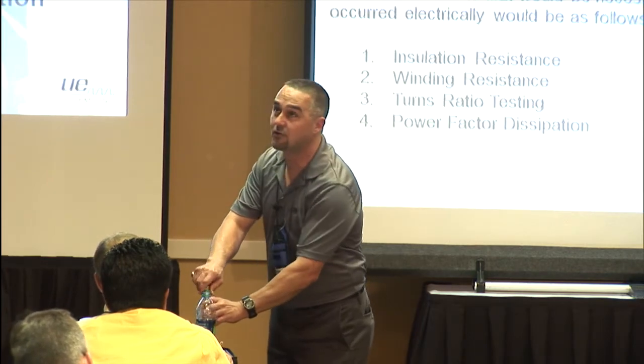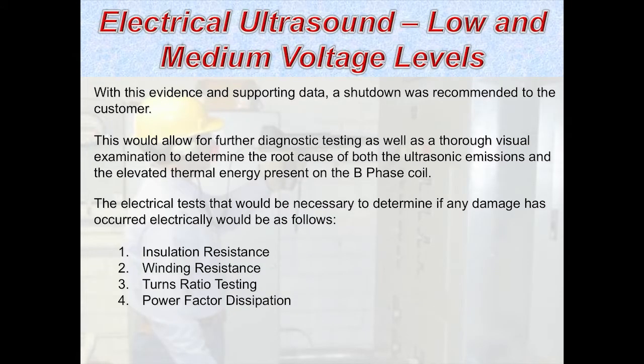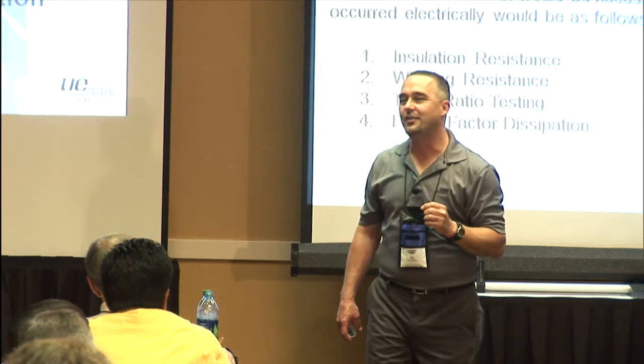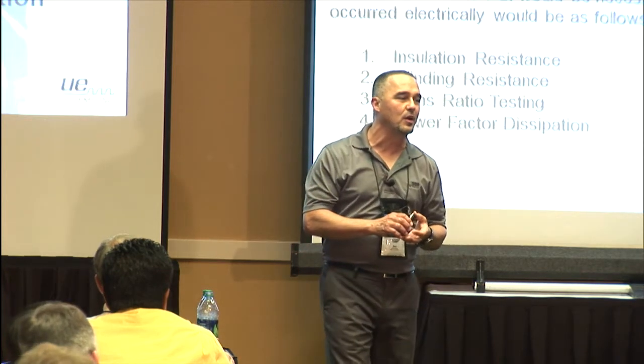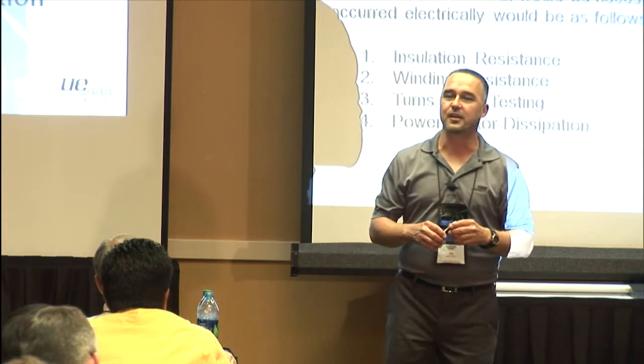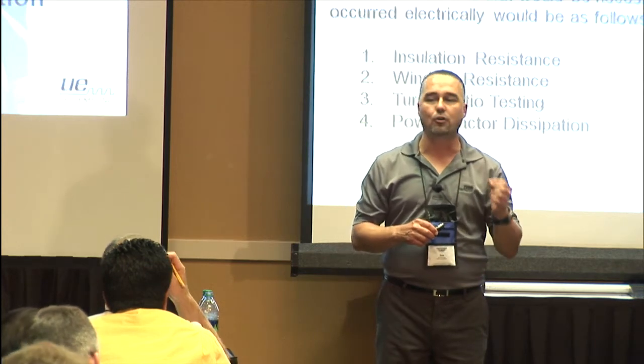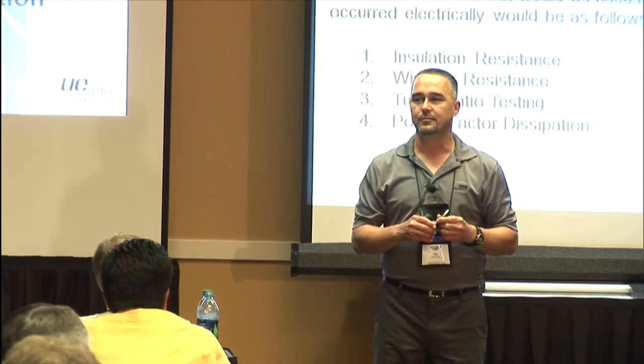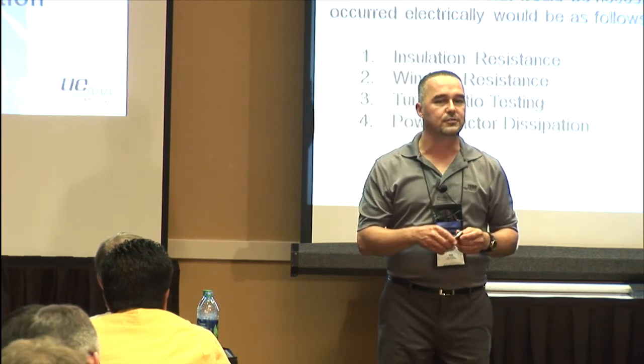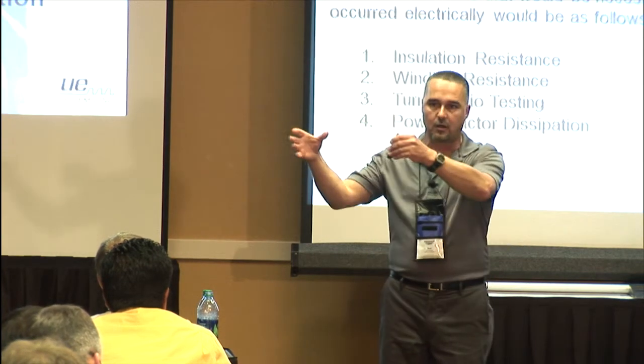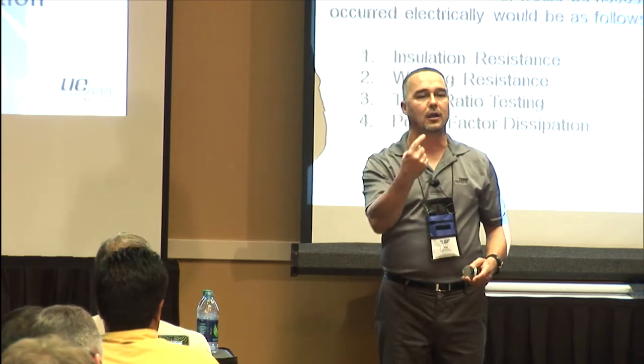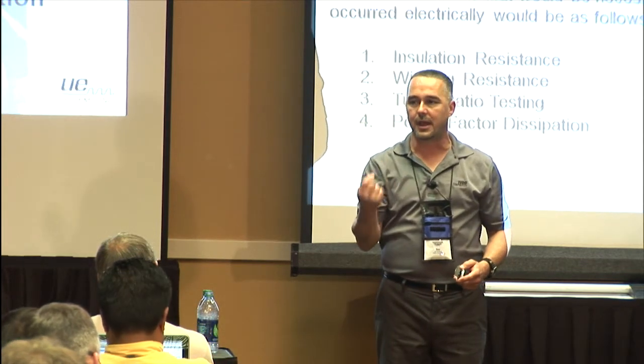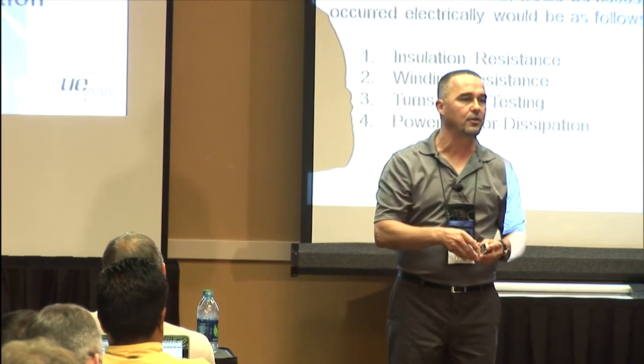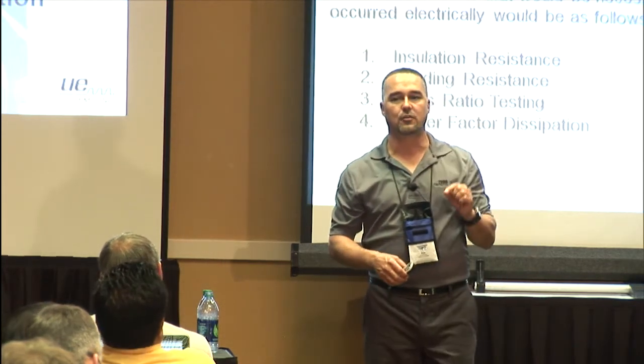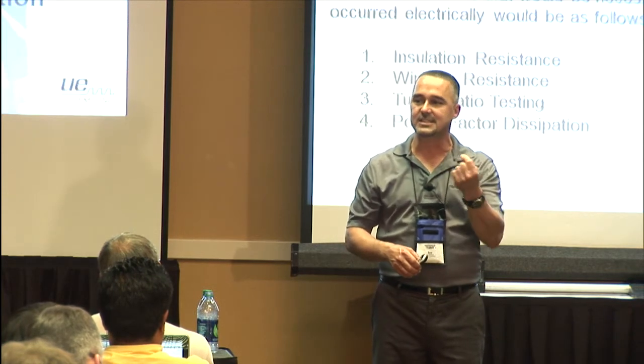The other one I got on here is called turns ratio testing. Has anybody ever heard of that? Good. Those of you who have not, a turns ratio test is the only test available to us to tell us a couple of things, but most importantly, are there turn-to-turn shorts within the windings? If you're familiar with the construction of a transformer, you know, you see them windings in there, and every one of them coils of wire are electrically isolated from the next one. They're wrapped in a varnish and baked in an oven and things like that. So they don't touch each other as they're wrapped and stacked.